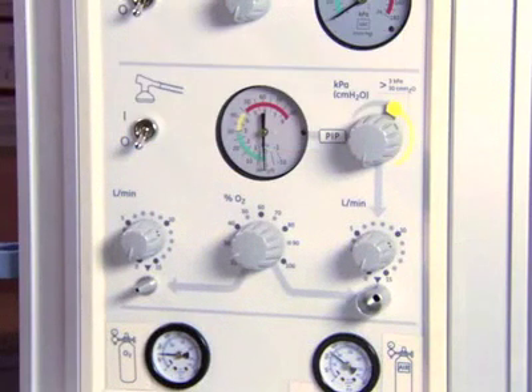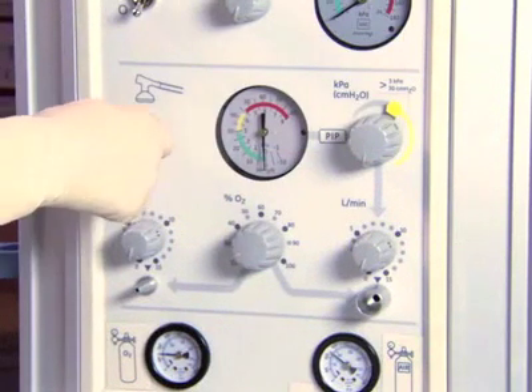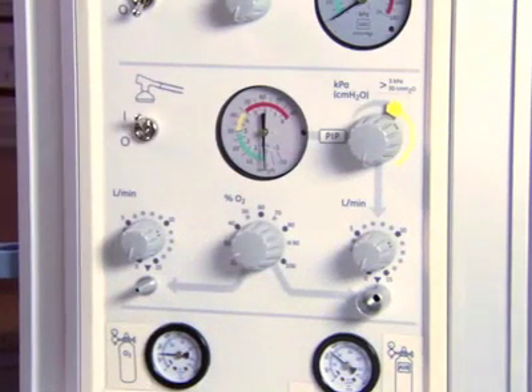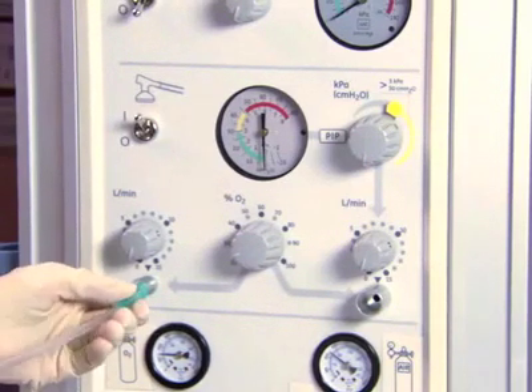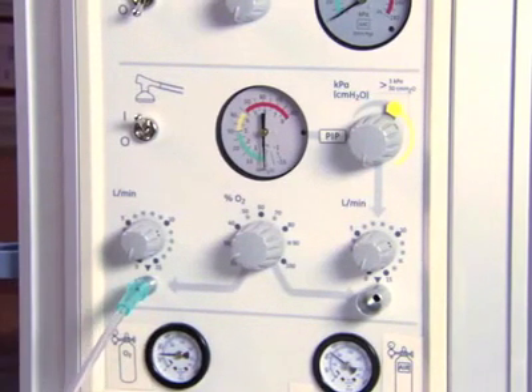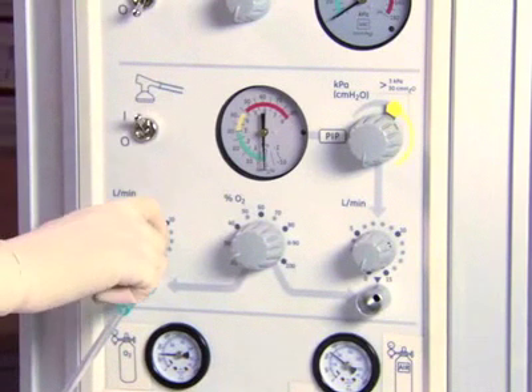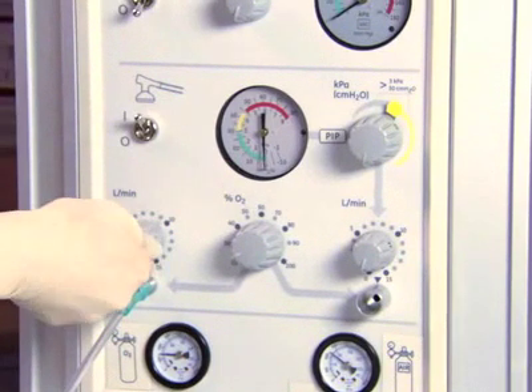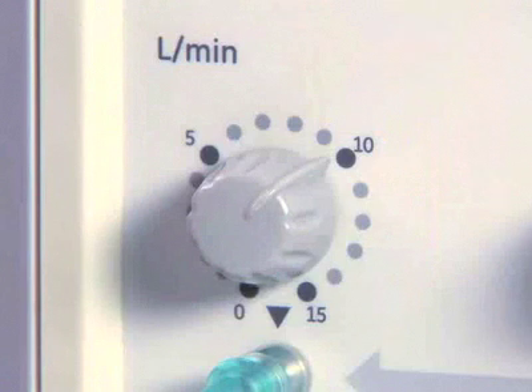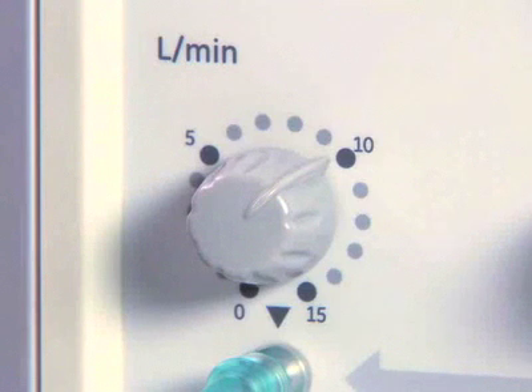Next, you will need to check out the T-piece resuscitation gas delivery system. First, turn the medical gas switch to on. Attach oxygen tubing for free-flow oxygen to the left gas outlet on the front panel of the resuscitation system. Turn the flow meter control knob above the free-flow oxygen tubing to a desired flow rate between 5 and 15 liters per minute. 10 liters per minute is effective in most cases.